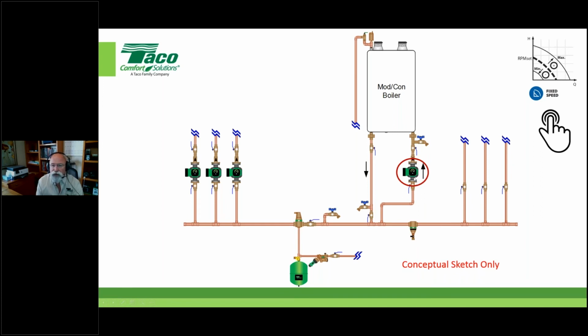So we'll focus on this circulator. I will say this while we're on this slide: the mode of operation—remember, these ECMs have all kinds of modes of operation. The only thing that makes sense in this near-boiler pump application is that 0 to 10 or 4 to 20 milliamp, or pulse width modulation, or some other method. One way or another, if you have that control, fine. But if you don't, there's only one other mode that makes sense, and every ECM has it: it's called fixed speed, sometimes called constant speed.